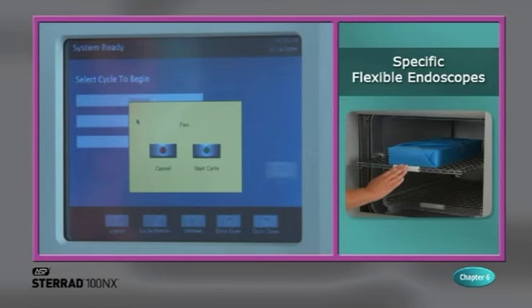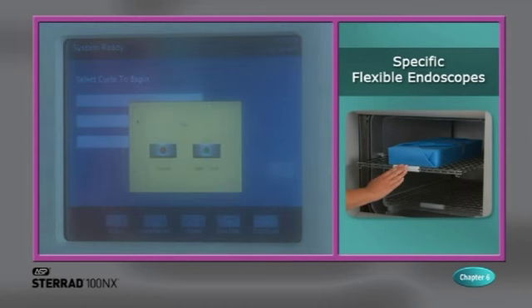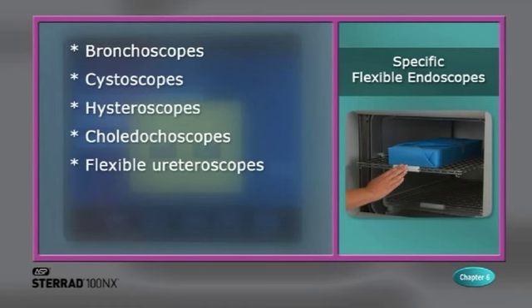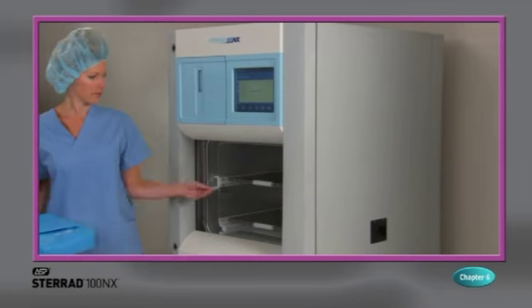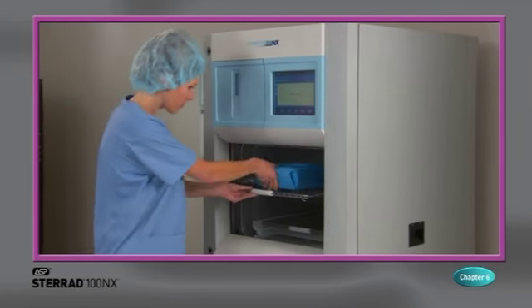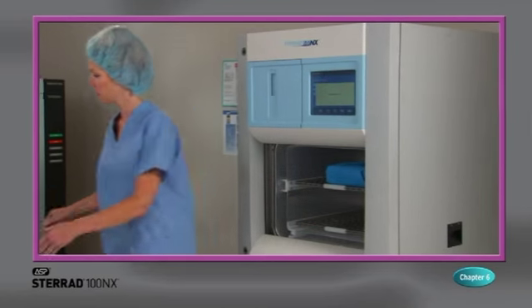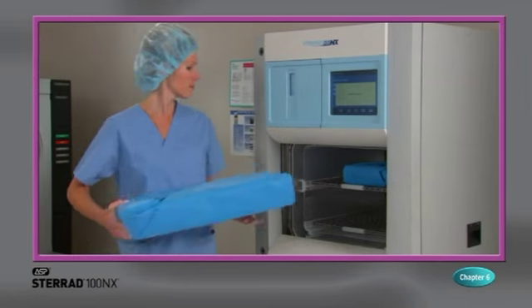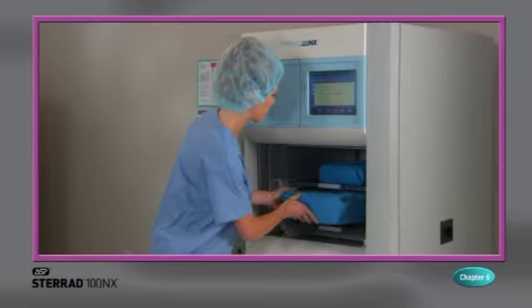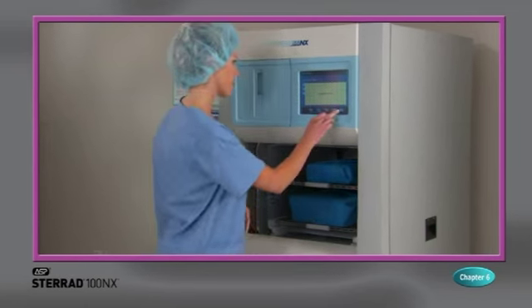Flexible endoscopes that can be sterilized in the flex cycle include, but are not limited to, bronchoscopes, cystoscopes, hysteroscopes, choledocoscopes, flexible ureteroscopes, intubation fiberscopes. In the flex cycle, you may load the chamber with a maximum of 2 single-channel flexible endoscopes at one time. No additional items may be processed in the cycle with the flexible endoscopes.